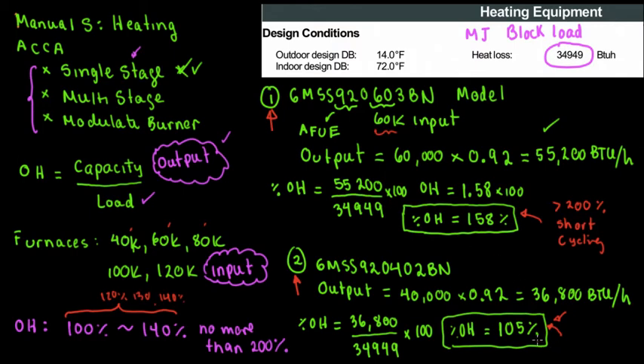Avoid short cycling. Don't oversize it so much. But also, this is good too, but sometimes there's a little bit of risk of this furnace not giving us enough heating. It depends also on the sensibility of the customer. Some customers want it harder, they want to have that control. That's why I'm choosing the 60K furnace. I know it costs more, but I'd rather be safe than sorry. That's why it's very interesting to utilize Manual S and know how to use this.